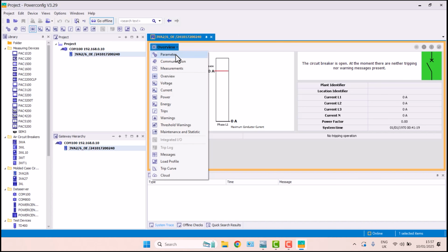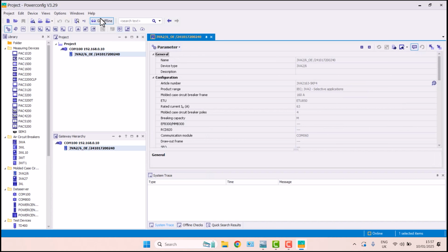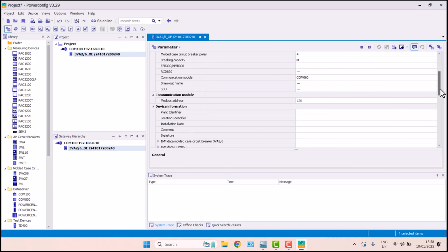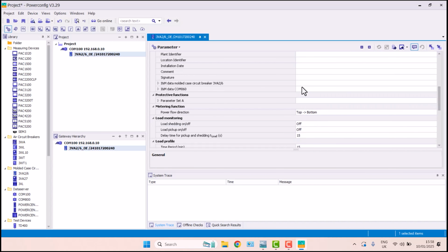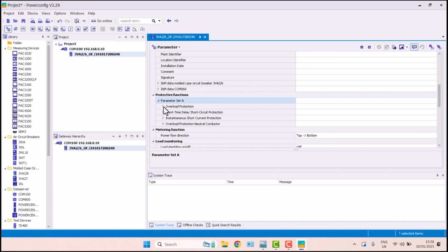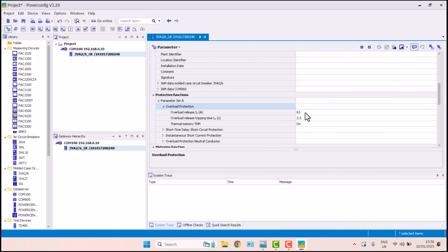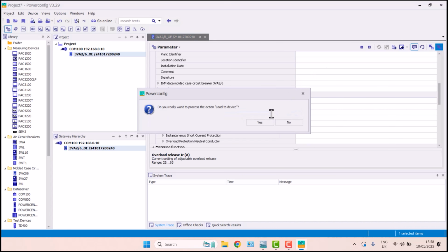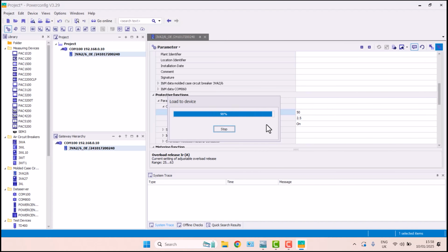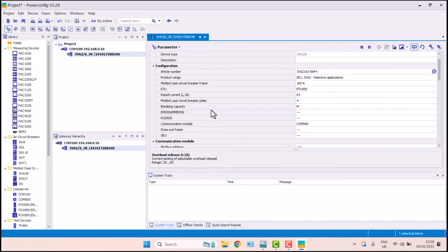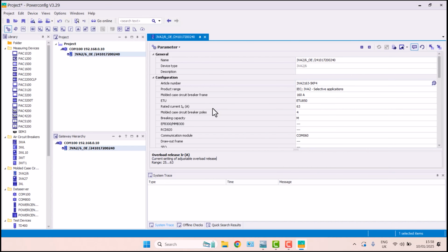If we want to make any alterations, this will be done in the parameter tab. You do need to go offline to make any alterations. Here we can select and rename the device, or we can change the ETU functionality. If we go to parameter set A, we can change things like the overload. So I'll change this to 50. To then save that alteration to the breaker, you need to download it to the device. There we have it. We have a COM100 and a 3VA2 all connected.